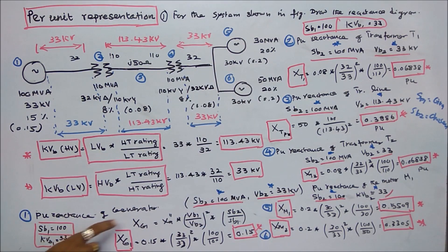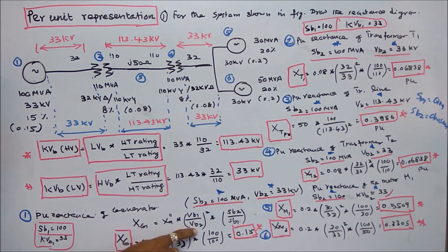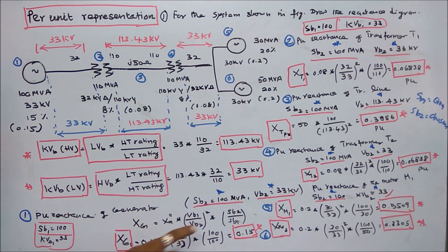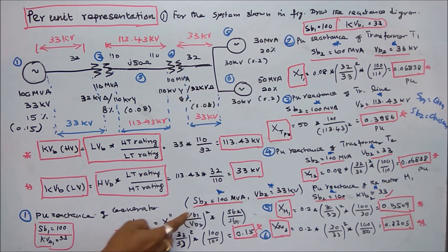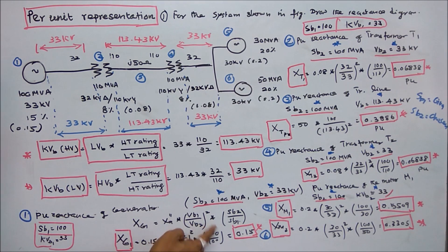First, find the per unit reactance of the generator. Xg1 equals actual reactance into (VB1/VB2) squared into (SB2/SB1). VB1 is given as 33 kV, VB2 is chosen as 33 kV, so (33/33) squared equals 1. SB2 is chosen 100, SB1 is given 100, so 100/100 equals 1. Therefore per unit reactance of generator 1 is 0.15.